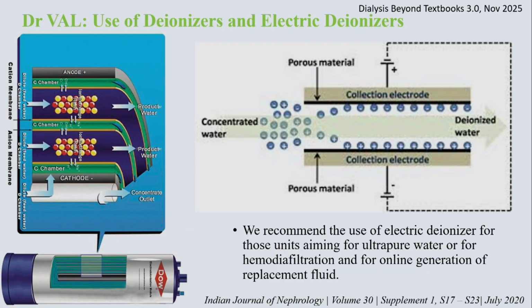What will be the cost of electrodeionizers? Yeah, so the smallest capacity one is about 3.5 lakhs. It's expensive, and if you're going to use an electrodeionizer, you must have a resistivity meter. Resistivity meters are about 30,000 rupees. Does the capacity apply here, or can it take any capacity? No, it obviously has a capacity depending on the size. The flow rate will depend on the capacity of the tube, so you have to choose the size based on your flow rate requirement.